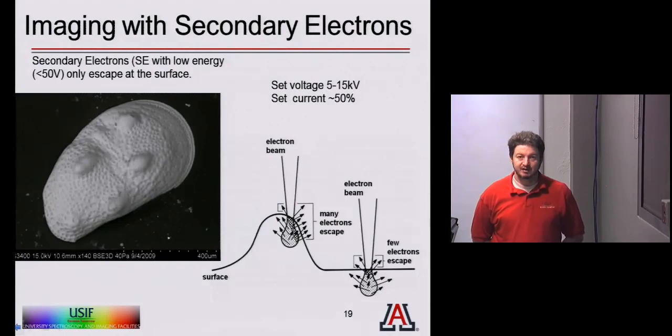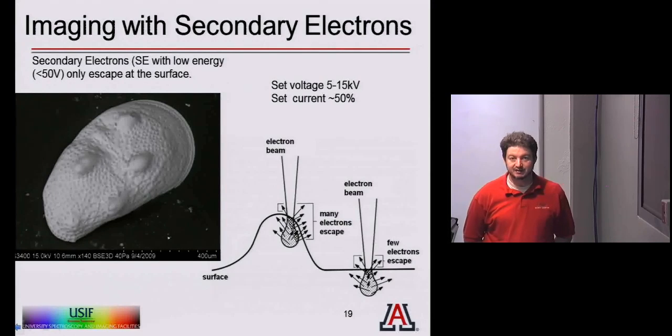To ensure conductivity, you can work with metallic samples, apply a conductive layer such as platinum, carbon, or gold, or operate the microscope in a way that neutralizes charge. The secondary electron signal is surface-based because at around 10 eV the electrons can only escape from the surface. The signal is topological — a flat surface gives a uniform signal, but bumps, edges, and slopes cause electrons to emerge from the top and sides, changing the yield. Divots appear dark due to lower electron yield, giving the topographic contrast that makes SEM imaging so powerful.